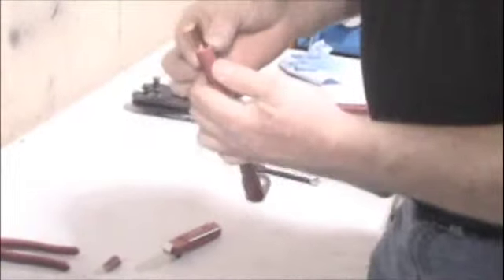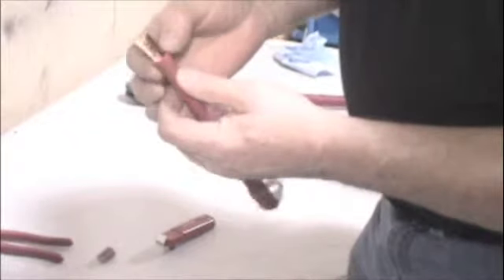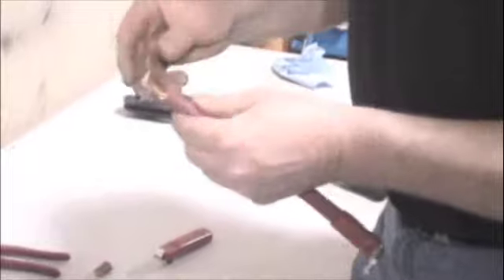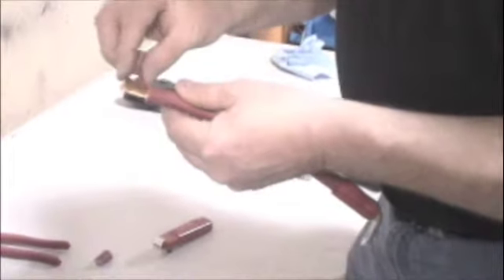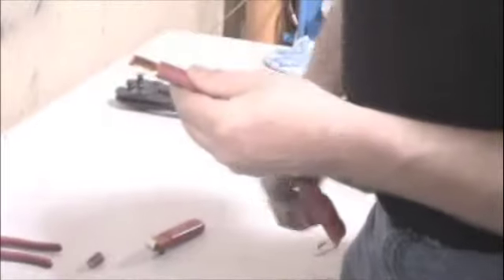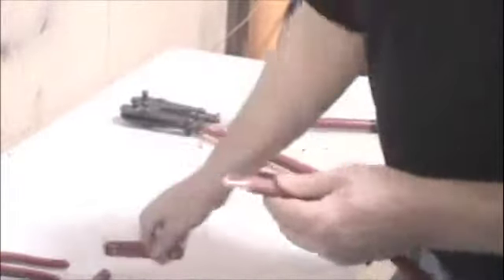And the reason you want to use one of these, when it's set properly it won't cut the cables. If you try and do this with a razor or with an exacto knife or with a utility knife, inevitably you're going to start to cut some of the cable strands and any cable strands we lose is going to cut the capacity, so we definitely recommend a cable stripper.